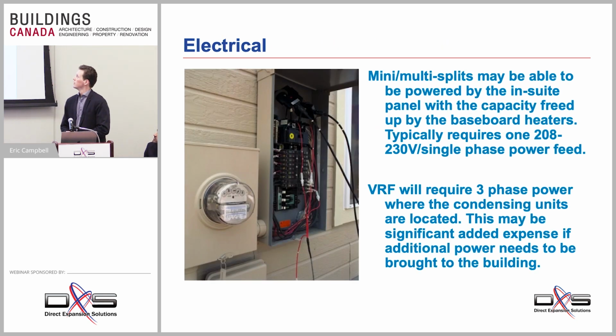What about electrical? There are differences between a decentralized and a centralized system in terms of how we power these systems. So with mini splits and multi splits, you've got one condensing unit serving one suite. If it's nearby, if it's on the balcony, something like that, it could often be powered by that suite panel. And now everything is easily metered. We only need one power feed for that condensing unit, which will power the indoor units. Fairly simple in that regard.